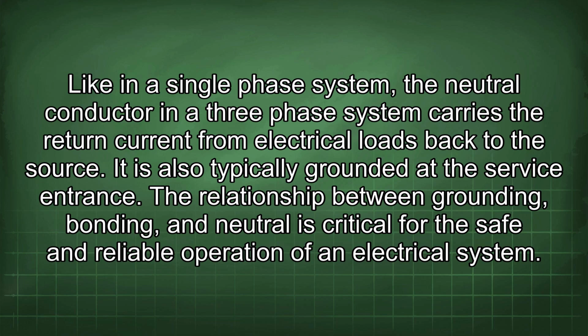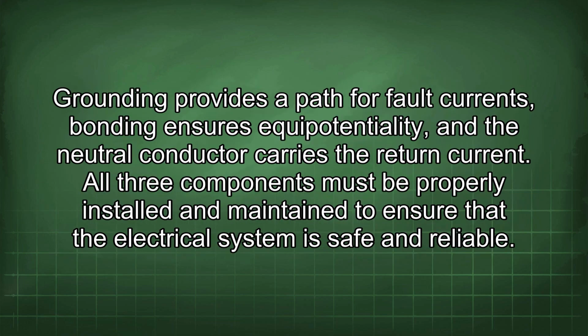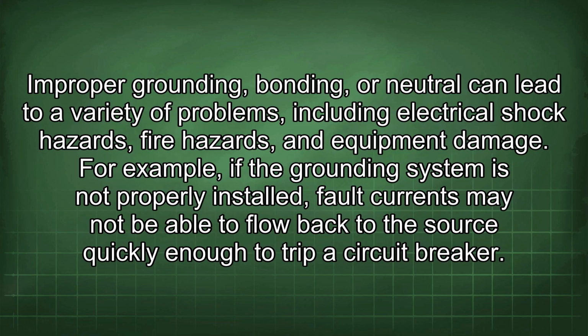The relationship between grounding, bonding, and neutral is critical for the safe and reliable operation of an electrical system. Grounding provides a path for fault currents, bonding ensures equipotentiality, and the neutral conductor carries the return current. All three components must be properly installed and maintained to ensure that the electrical system is safe and reliable. Improper grounding, bonding, or neutral can lead to a variety of problems, including electrical shock hazards, fire hazards, and equipment damage. For example, if the grounding system is not properly installed, fault currents may not be able to flow back to the source quickly enough to trip a circuit breaker.